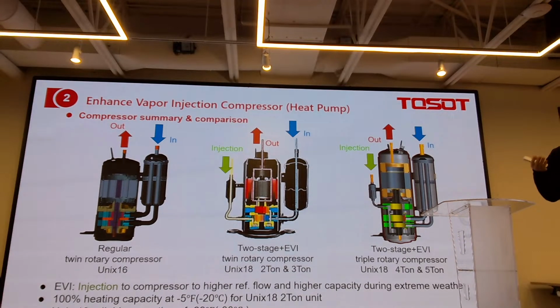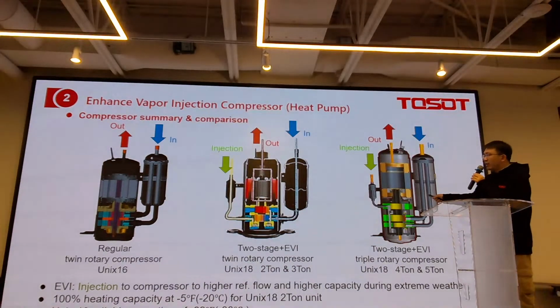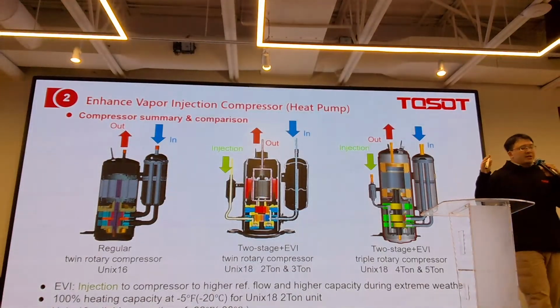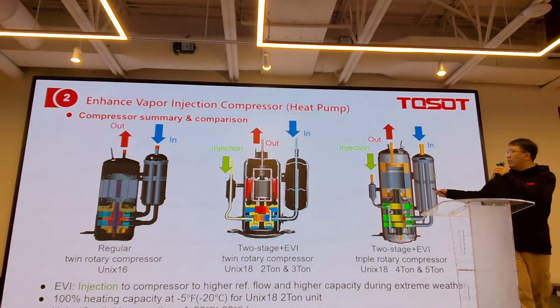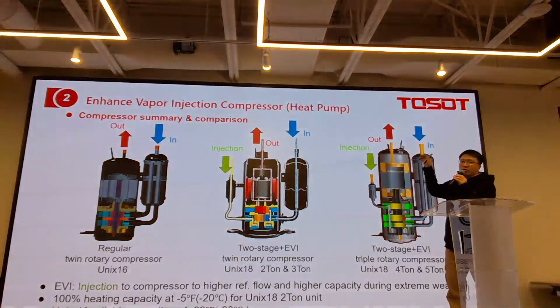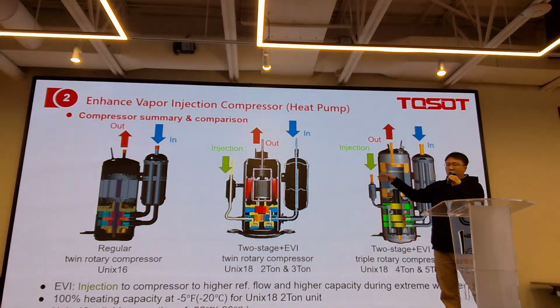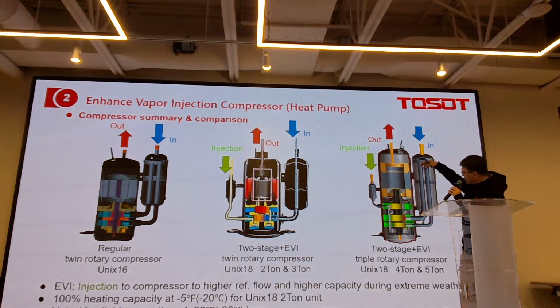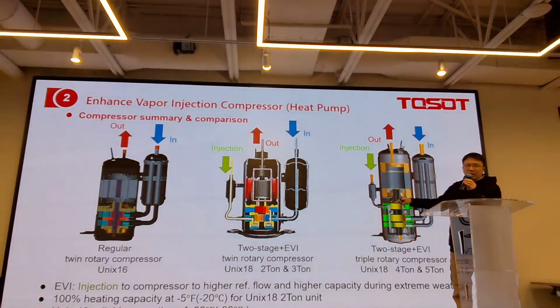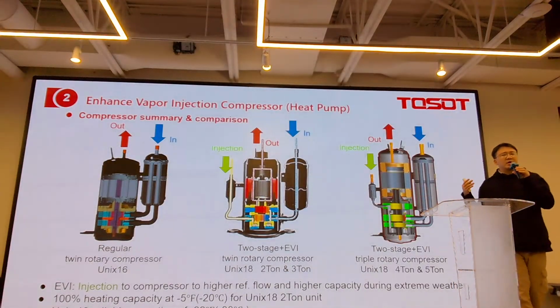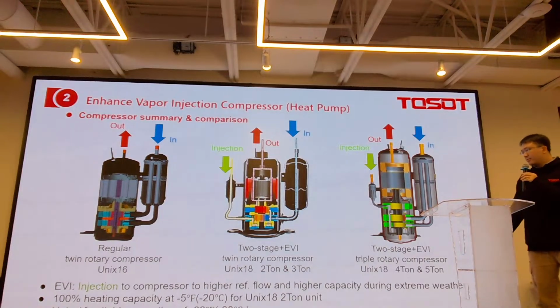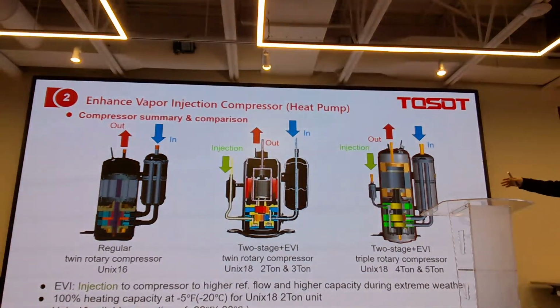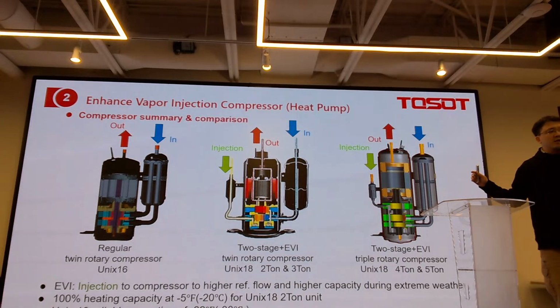You don't have enough heating capacity. Right. In other words, the air blowing out from the indoor side will be very low, and the customer will just complain that the equipment is not heating. And that's the reason, if the outdoor ambient is low, let's say less than the freezing point, then we will turn on this injection, which is to inject some more refrigerant into it. You can also find that if you inject here, then you will have another bypass to here. The purpose of it is just to increase the refrigerant flow rate. And that is also the reason why the Unix18 can work until -30.